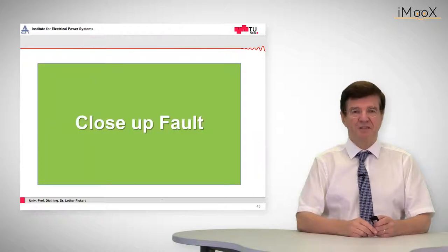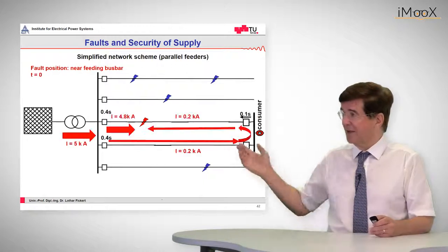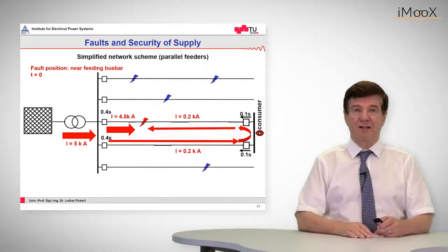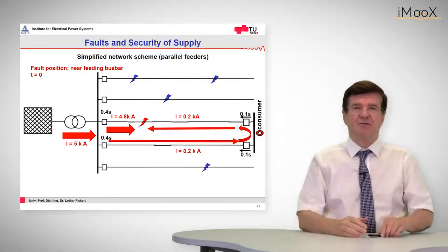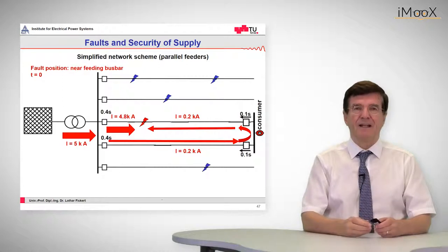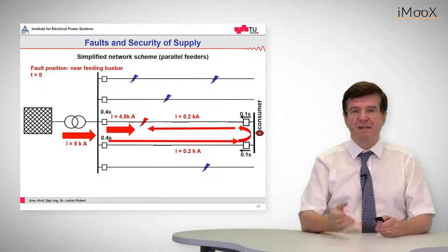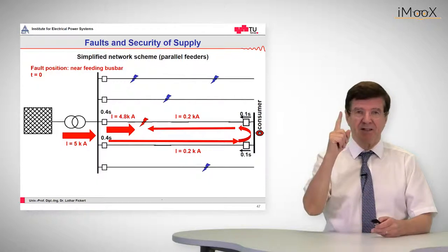The situation is different if we have a close-up fault as is indicated here. If the close-up fault occurs, we have a split of the total current of five kiloamps into a big current which goes directly to the faulty place and a smaller one that goes all the way around. And that may be, as indicated in this case, too small to start up any of those relays. So there is just one relay picking up, that's the upper one.